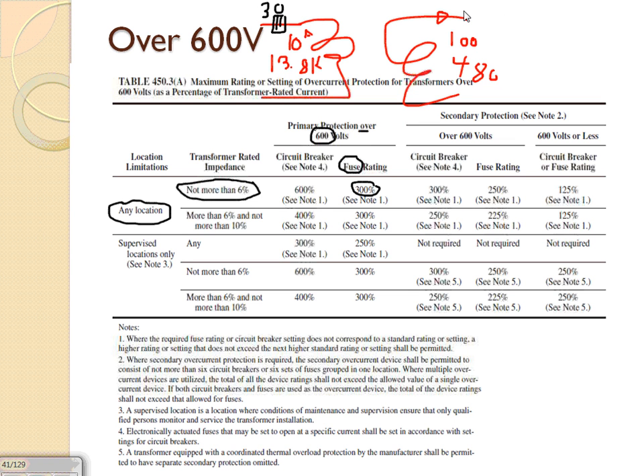If you go to the secondary side, it is less than 600, 600 or less. I'm using a circuit breaker, so my multiplier is 125. So this is going to be a 125 amp fuse. Straightforward, done. This is the most important table to size fuses for the primary and secondary of a transformer. What I highlighted is the most common application. Supervised locations are another set, but if you don't know anything about the location, that's where you default. Any comments or questions about that?